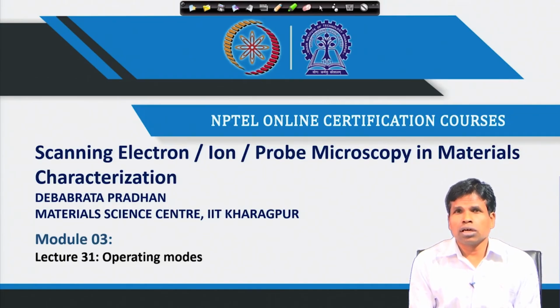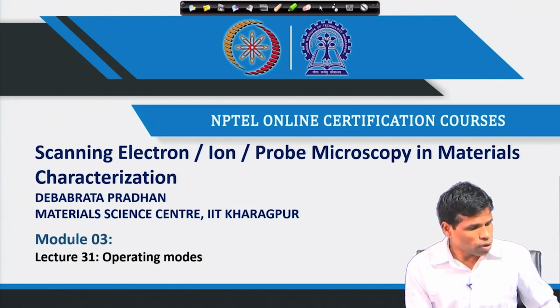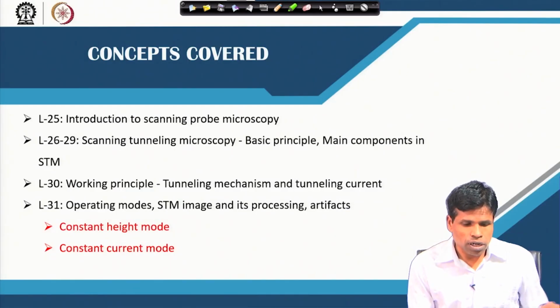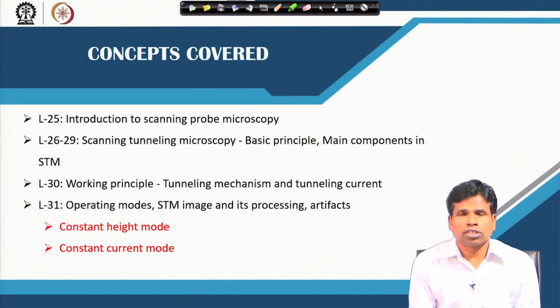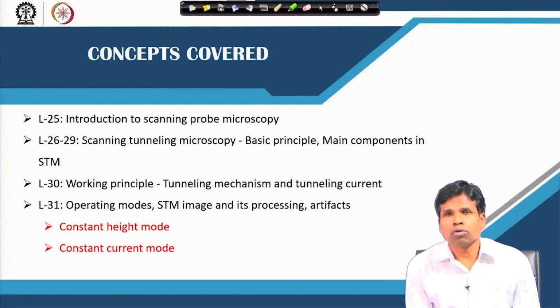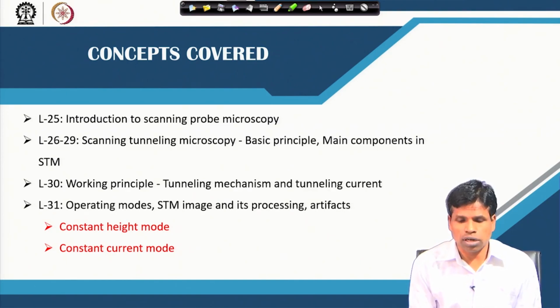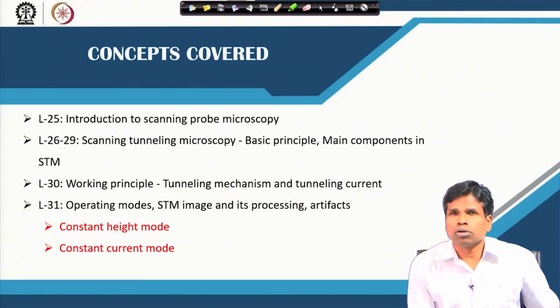That we will see today in the operation modes. There are a couple of operation modes, particularly constant height mode and constant current mode, and these two modes are normally used to get the surface image in the scanning tunneling microscope. In addition to that, I will show you what type of image is obtained in the scanning tunneling microscope and how the image is processed briefly. There can also be some artifacts, so how one can know the presence of artifacts in the image and how to get rid of those artifacts.